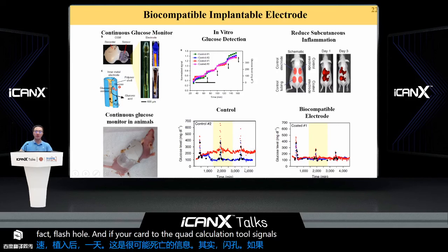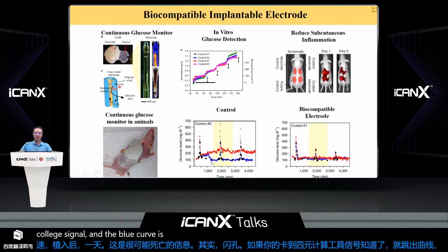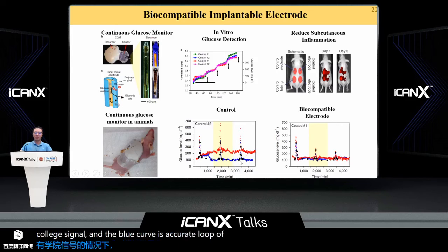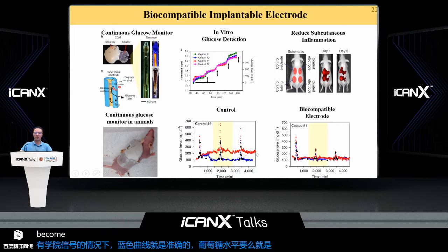of the implanted electrode, which required calibration to collect the signal every day. As the result shows, the red curve indicates the recorded signal, and the blue curve is the accurate glucose level calibrated by the blood test. We can see that the signal becomes inaccurate quickly after one day.